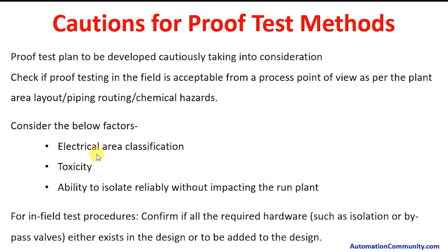Consider factors such as electrical area classification, toxicity, and the ability to isolate reliably without impacting the running plant. The running plant shall not be disturbed for proof testing requirements, and this must be kept in mind. For in-field test procedures, confirm if all required hardware such as isolation or bypass valves either exists in the design or needs to be added. If there is no bypass available, an alternate method must be developed before performing the proof testing.